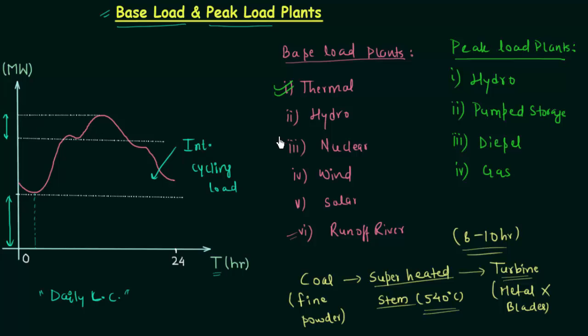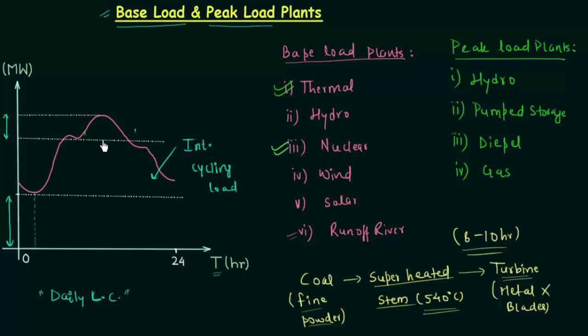The same applies to nuclear power plants — the time is not exactly the same since we don't crush coal but use radioactive materials and nuclear fission to produce superheated steam, but it still requires significant time. So to satisfy peak load using thermal power, you would need to know the timing 8 to 10 hours in advance. By the time the plant starts producing electricity, the peak load is already gone. That's why we don't use thermal or nuclear power plants to satisfy peak load — we use them as base load plants.